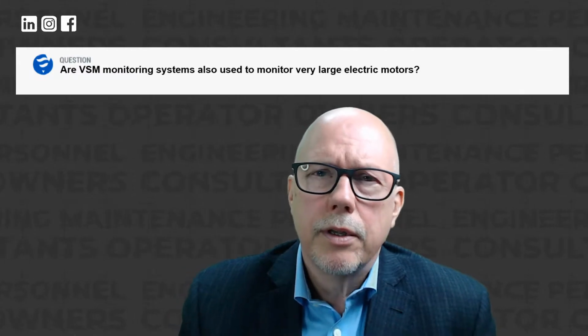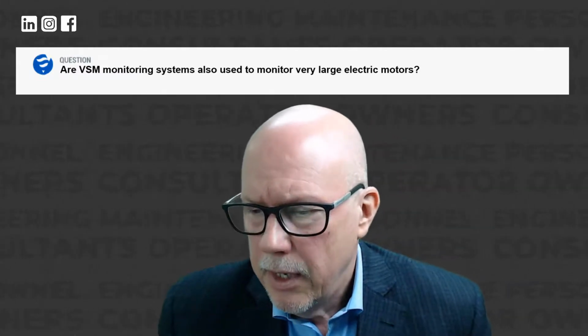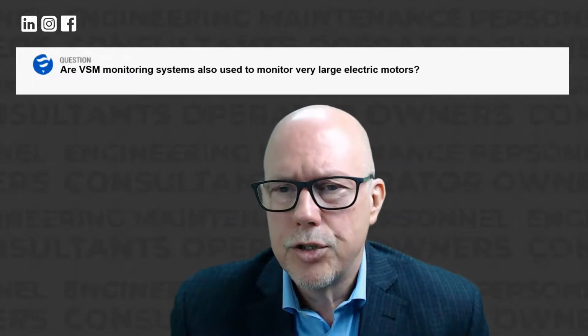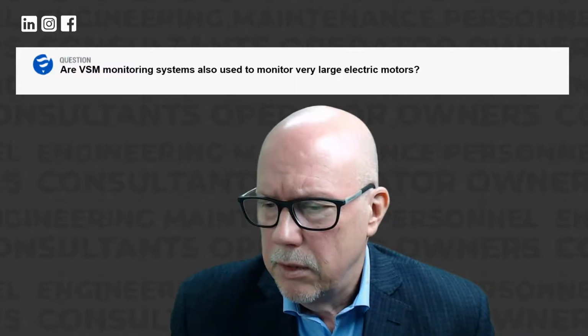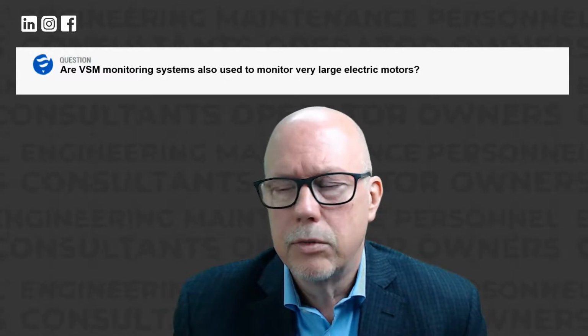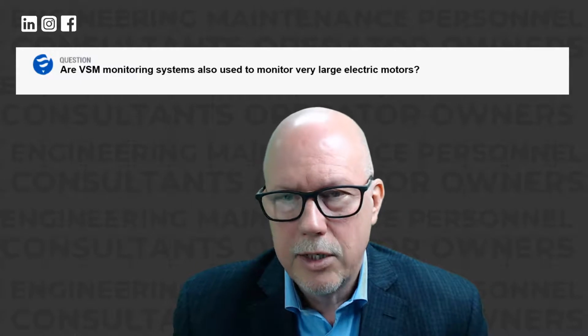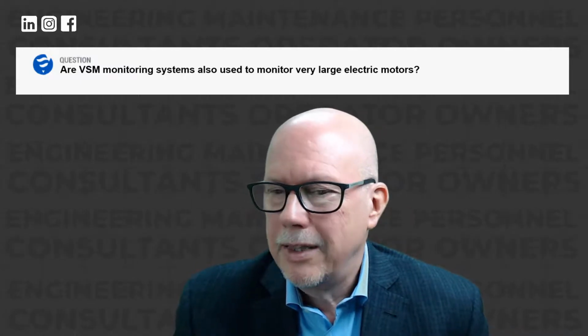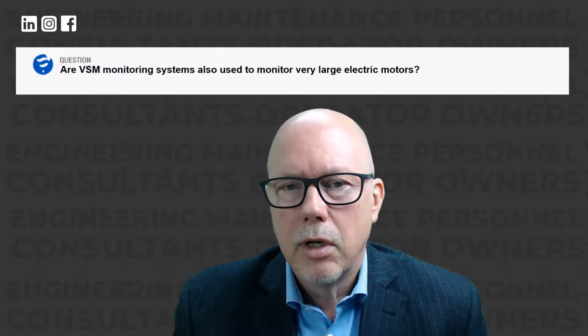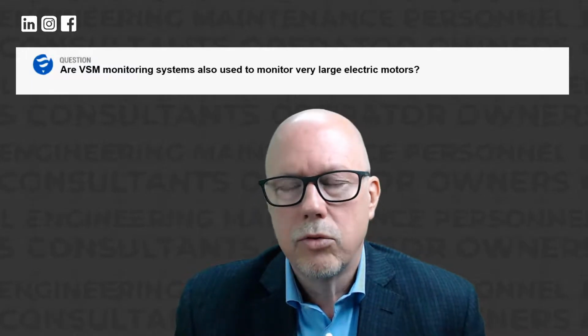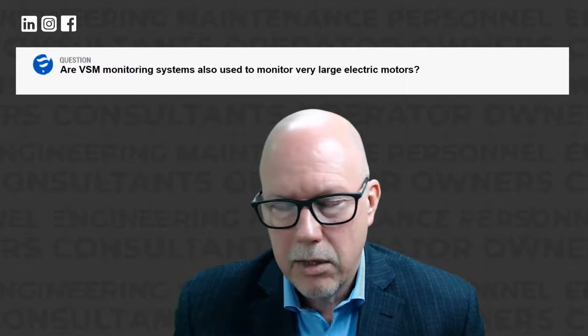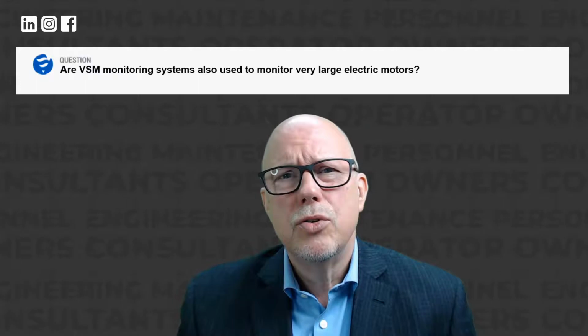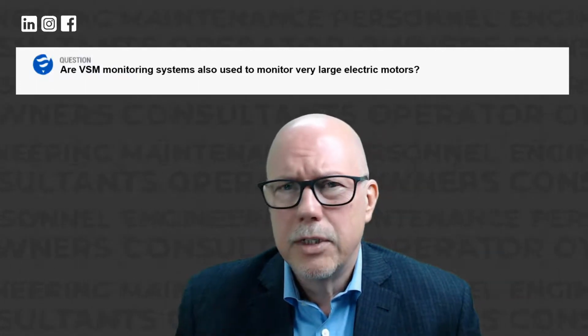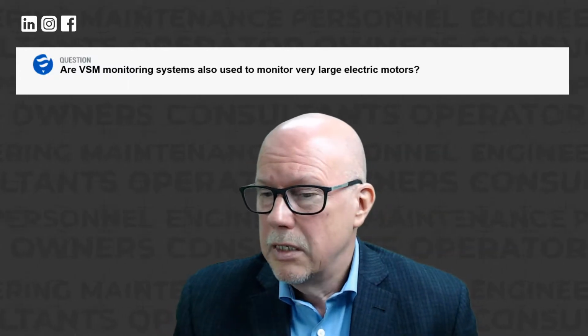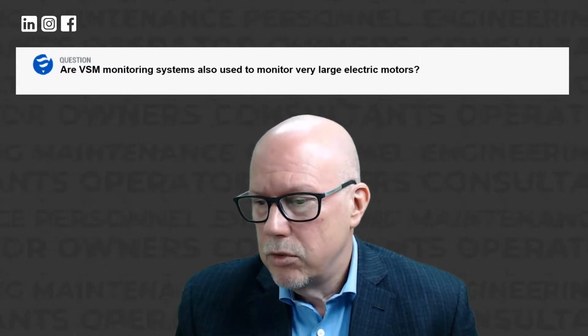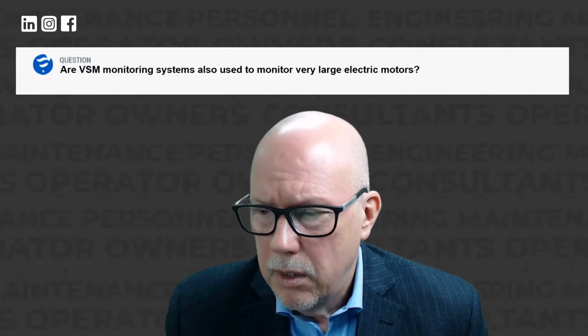We've been very fortunate to work with very competent mining engineers, and we've helped them significantly find all kinds of issues on their units and try to improve their performance. The mining industry produces a tremendous amount of revenue, and long unexpected outages are a tragedy to them. It's a problem to everybody, but in their case, it's a lot of money. They do not want to stop their mills for no reason, and when they go through outages, they want those to be as efficient as possible. We found all kinds of temperature issues, vibration issues, bearing oil film issues, serious rotor pole issues, serious stator core and frame issues, and we've actually started to help them replace their poles.